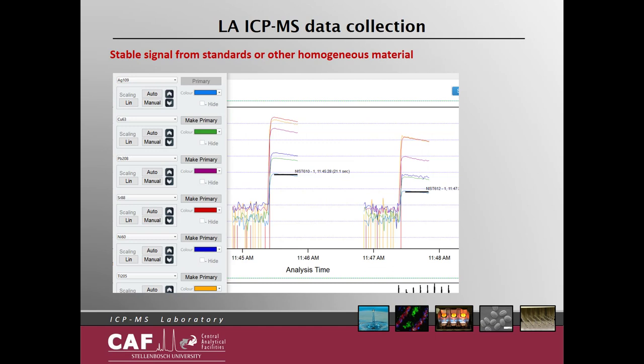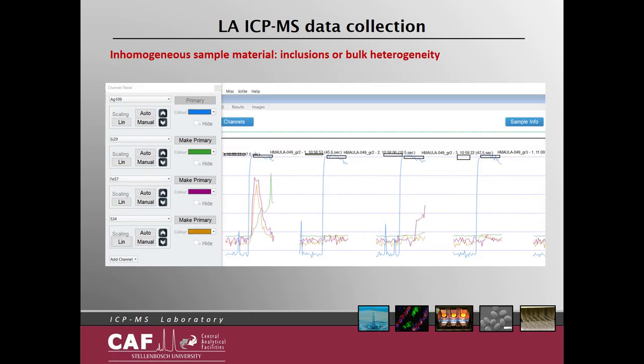Typically you would like to see a stable signal for all elements for the duration of the ablation. However, this is not always the case. Sometimes you can have an ablation signal with several elements increasing or decreasing at the same time, or independently, which is a clear indication that the sample material the laser is drilling into — at a rate of about 3 microns per second — is not homogenous. The way ablation data is acquired as a time-resolved signal is very useful to identify such features, and explains why repeat measurements could all produce different results as seen from four different ablations on the same sample material.